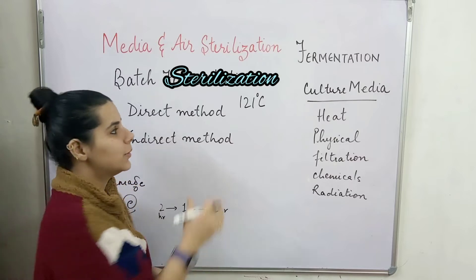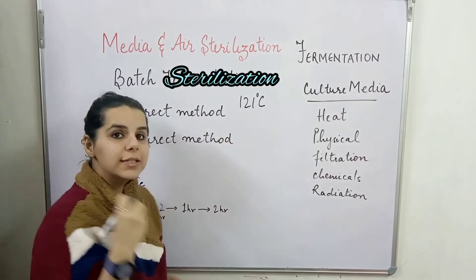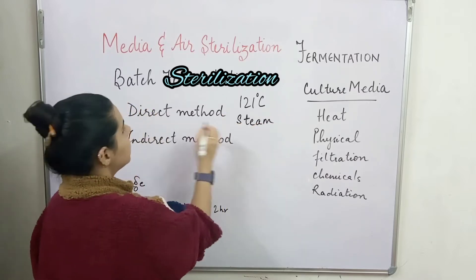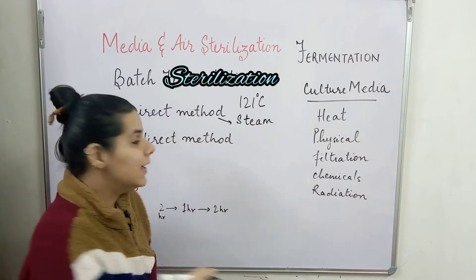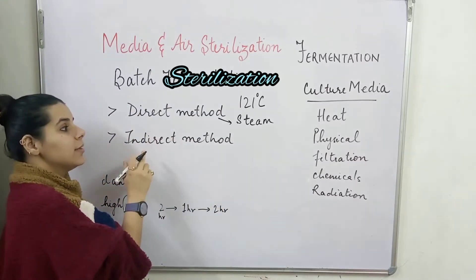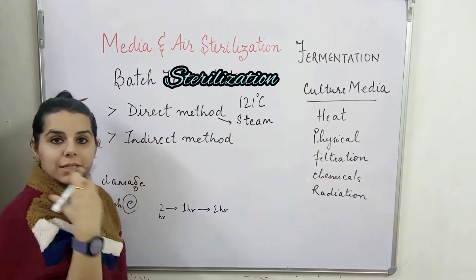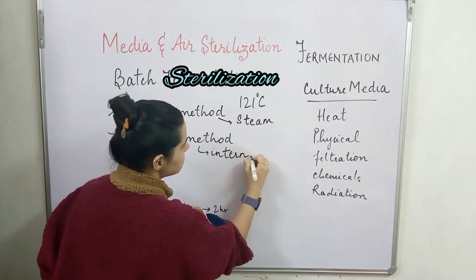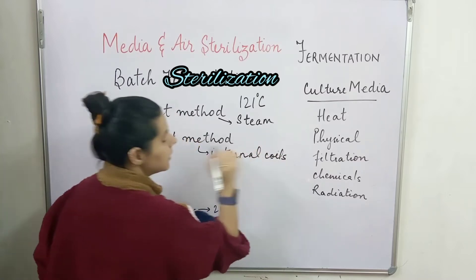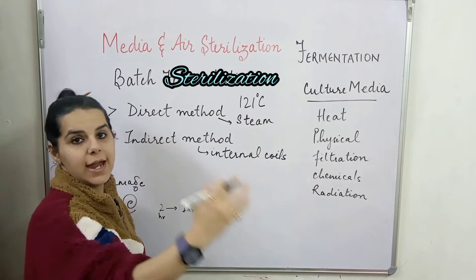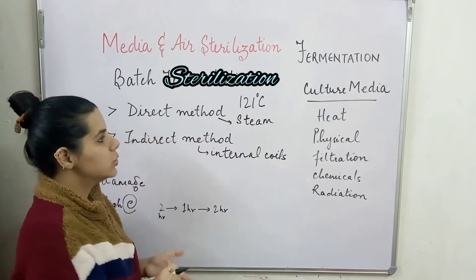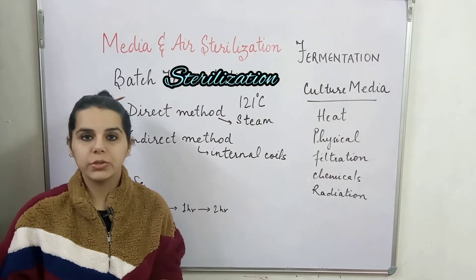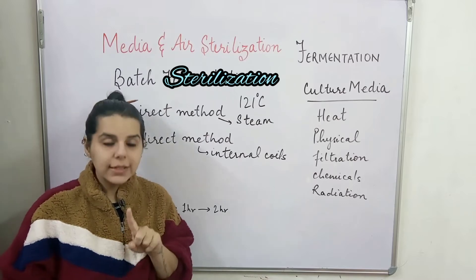In the direct method, we directly inject the steam. In the case of the indirect method, the steam is passed through internal coils that are internally present, and through these coils the steam is passed and the sterilization process occurs.